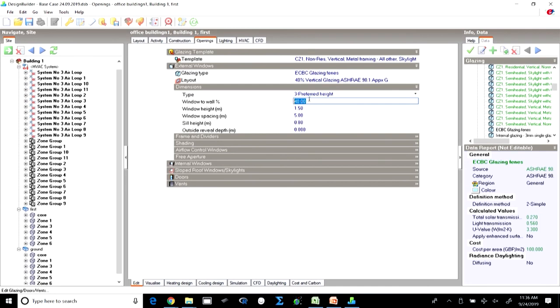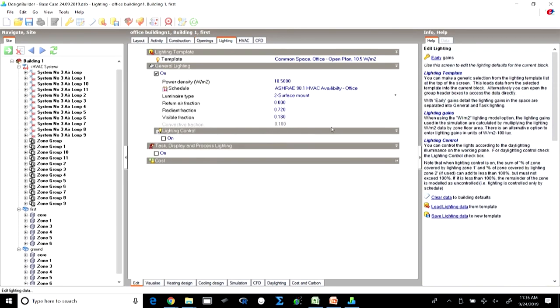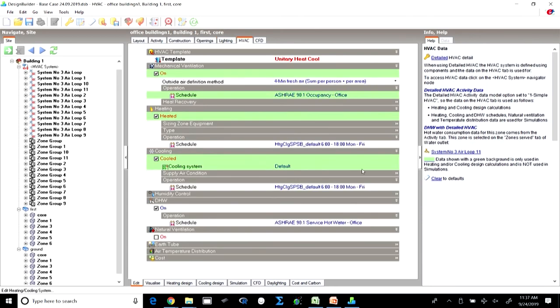We modeled the openings as per ECBC — the WWR maintained at 40 percent, with windows uniformly distributed. We selected the fenestration and glazing with prescribed values as per ECBC for the composite climate. For lighting we took 10.5 W/m² for the office area while for the core we changed the schedule. The lighting power density of 10.5 W/m² is prescribed in both NBC and ECBC. The schedules were changed, and for HVAC we followed the ASHRAE prescription and used System 3.